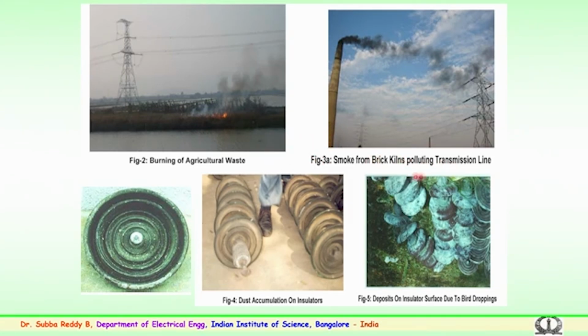The second is brick kilns or very highly polluting industrial areas, where smoke coming into the atmosphere could settle on the surface of insulators nearby. Transmission lines of extra high voltage and ultra high voltage get polluted, or the surface accumulates pollutants, and after becoming wet this could lead to flashover.